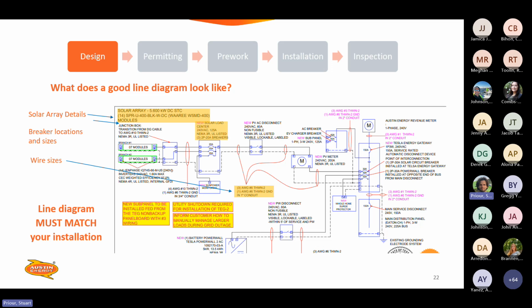That's a common point of confusion for contractors, is that the solar is going to land on the line side of your PV meter and the load side of your PV meter is going to go to your interconnection point. They've also done a good job at calling out the existing service specifications there. They've got a main breaker, and they've called out downstream of their interconnection what equipment is also existing on site. You can see there's a stamp here. That stamp is there because this is a battery project. There's an ESS there, and we require engineering stamps on any projects that involve energy storage systems.